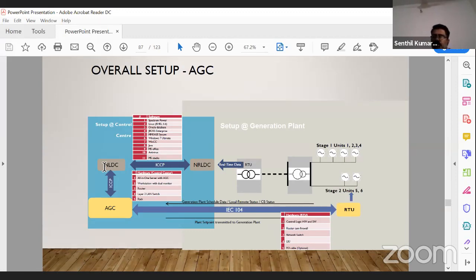If the automatic generation control setup is available in the state load dispatch center, regional load dispatch center, or national load dispatch center, it is possible to increase generation from the control center itself for remote areas. Suppose the generator plant is in a remote area; through SCADA and AGC control, we have to increase the generation within a shorter duration. This is possible with implementation of AGC.